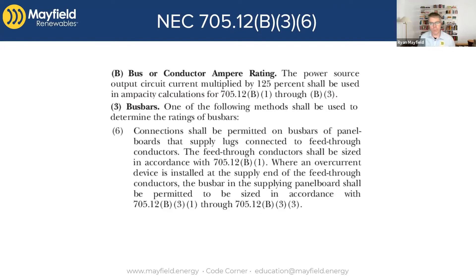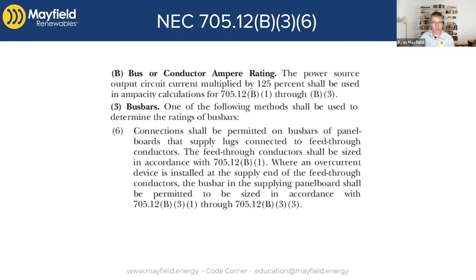This is a really common installation that we see. A lot of systems have meter mains with feed-through lugs that then feed a sub-panel in the garage or somewhere else in the house. The solar connection is a lot easier if you can get inside that meter main, but the issue becomes how we treat that downstream panel, conductors, and all those things.